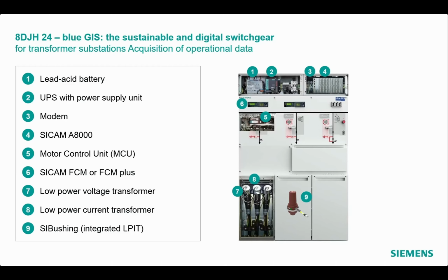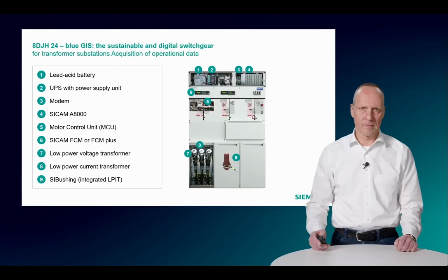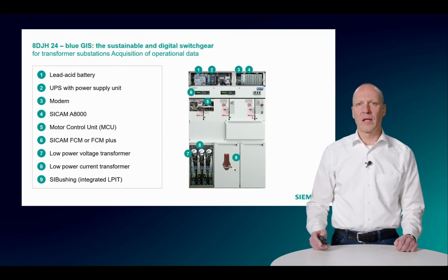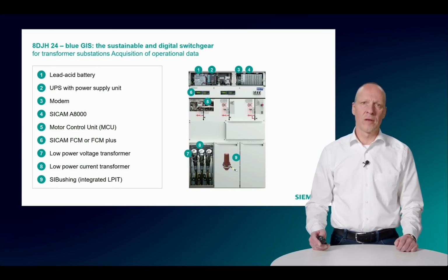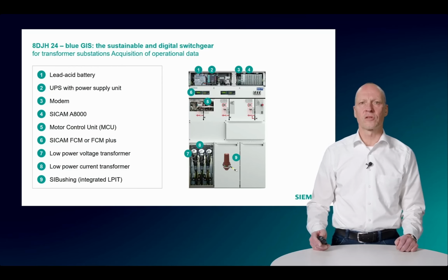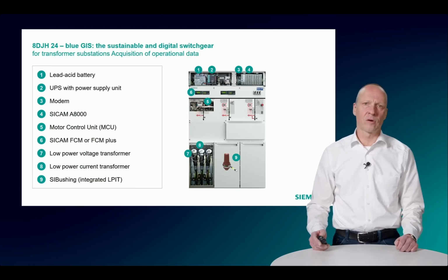Starting from the top, we have a minimum 200 mm low voltage compartment on top of the switchgear. To ensure an uninterruptible power supply, a battery buffer, for example in lead-acid technology, along with a power supply and DC UPS module is a must. Depending on the available physical communication, the appropriate communication modem must be installed. To collect all the information from the switchgear and to receive all the control commands from remote, a centralized gateway like our SICAM A8000 RTU is mandatory. To control the motor of the 3-position switch, a motor control unit is installed which is not visible from the outside. In the ringmain unit cable feeders, there is typically installed an intelligent short circuit and earth fault indicator, such as our SICAM FCM or FCM Plus.